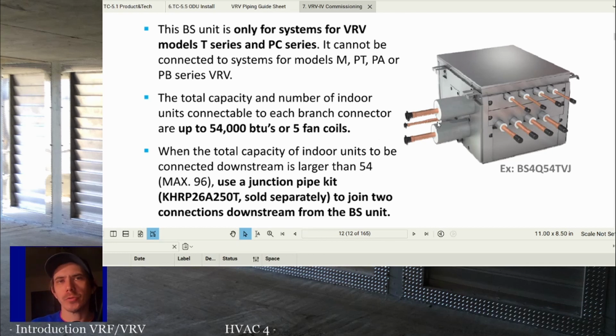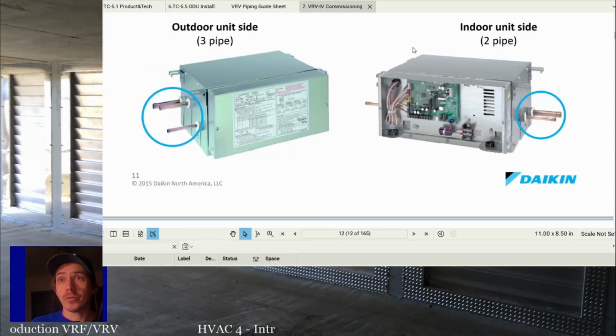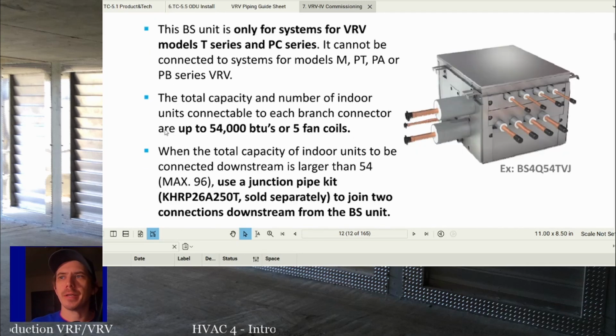So you have 3 ports coming in from the outdoor unit, and then you have 1, 2, 3, 4 ports to go to the indoor units. So you have the outdoor unit pipes going into the branch selector, and this can serve up to 4 indoor units off of a single branch selector box. We'll see a piping diagram and I'll explain it. But this allows you to connect these indoor units separately, and there are individual solenoids, so all these units can be in heating or cooling. These two can be heating, these two could be cooling, or it could be heat, cool, heat, cool. There are separate solenoids in this box for each set of units. It's a way of making it so you're not running as much three pipe, you're not installing as many Y kits and things like that, and you're consolidating your piping essentially.